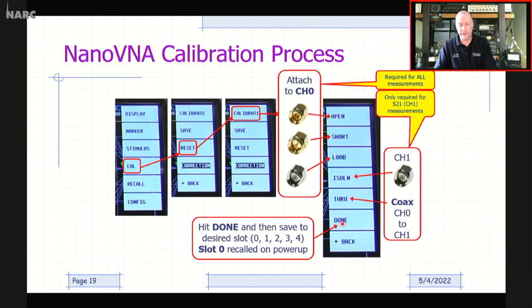Again, they're required for all measurements. And then the isolation and through measurements are where we actually apply a termination to channel 1 to keep it from receiving stray energy, and therefore we can measure the crosstalk between port 1 and port 2 inside the VNA. And then the through measurement is connecting the 2 ports together, okay, so we can measure the source, for example, and apply those corrections. So once you've done all of these, then you hit done. And when you hit done, it'll prompt you to save the calibration into the desired slot, 0 through 4. Later firmware versions actually have more slots.